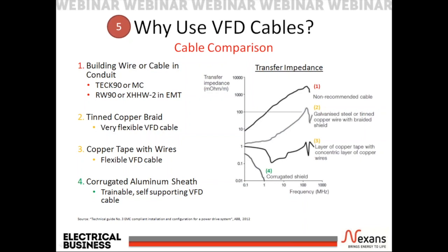Looking at one of the more flexible VFD cables available in the market, tinned copper braid VFD cables, higher frequency impedance is marginally acceptable, but there may be applications where cable flexibility is of utmost importance. An example of this would be robotic arms. This cable is acceptable for use as a VFD cable.